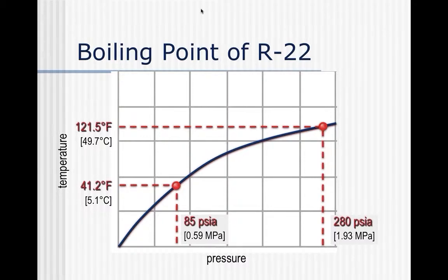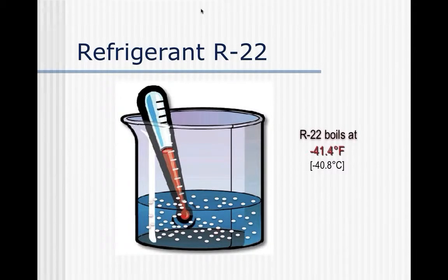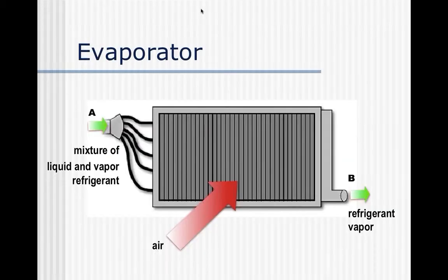But when you boil water, the transition from water at 212 to steam at 212 takes how many BTUs? Anybody remember, for a pound of water? I don't remember. 1200 or 593, I get my units mixed up, but it's a lot, right? So when you send that steam somewhere and the steam condenses, it releases an enormous amount of heat. It's very efficient to move heat using steam. Okay? And it's also efficient to move heat, cooling, using refrigeration. So here's our refrigeration cycle.